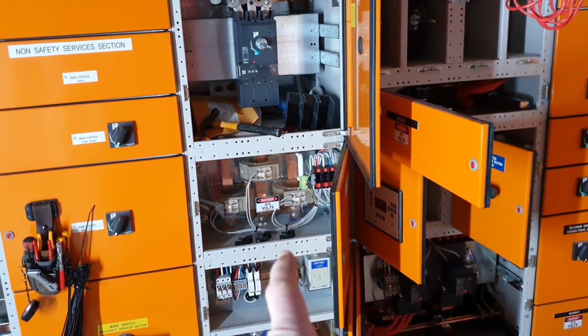But when the inspector comes, he's going to disconnect the MEN link and say, 'Oh, you've got a connection between the two,' and if you can't explain it straight away, he's going to go, 'That's no good, there's something wrong with the board.' So it meant pulling apart this switchboard trying to find things.